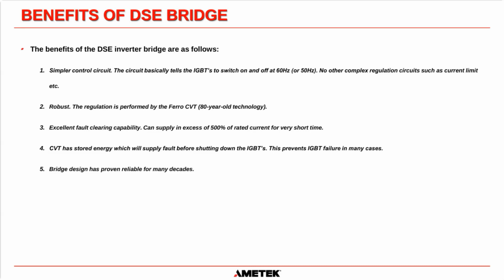The CVT also has stored energy, which will supply power to the fault. The energy in the transformer supplies the power, and we can shut the IGBTs down quickly, and that prevents IGBT failure in many cases. Not every case, because I've told you before, the IGBTs are very, very sensitive. But it is designed in. As soon as we see an issue, we shut down the signal to the IGBTs, and then the stored energy in the transformer will supply the power to the fault, clear the fault, and you'll probably transfer to bypass in that short period of time, and then you can go back to inverter. But we're trying to protect the IGBTs in that case.